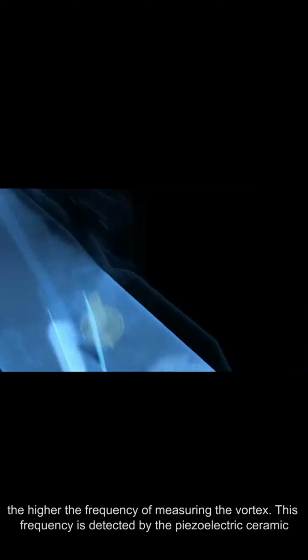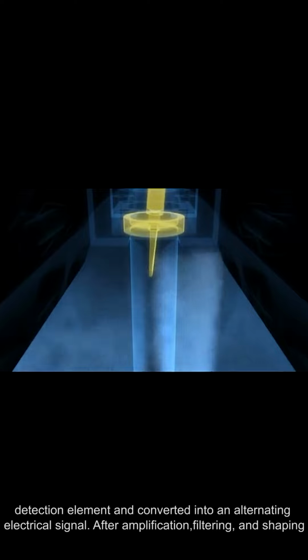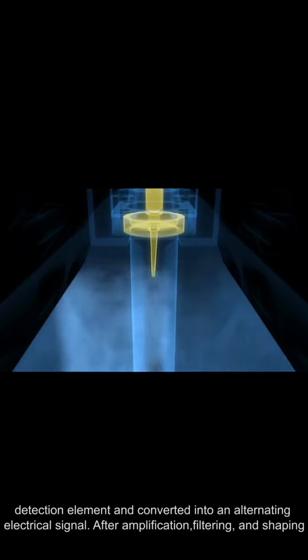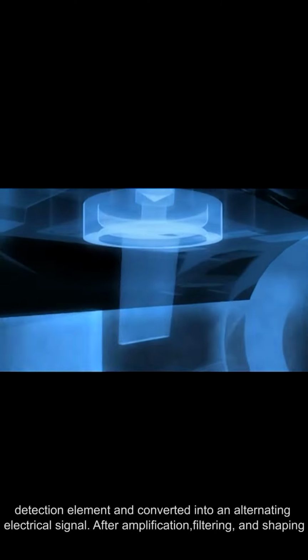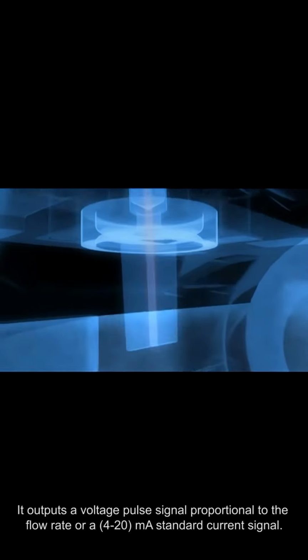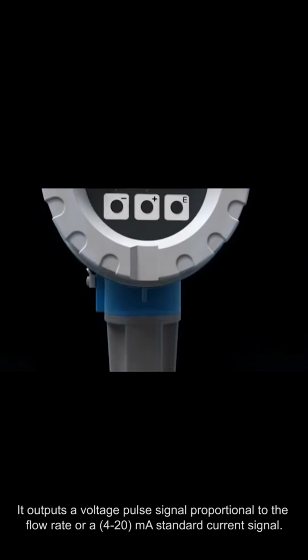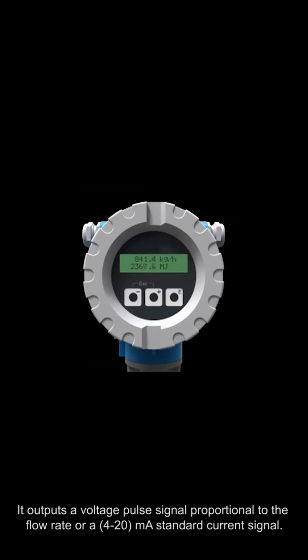This frequency is detected by the piezoelectric ceramic detection element and converted into an alternating electrical signal. After amplification, filtering, and shaping, it outputs a voltage pulse signal proportional to the flow rate or a 4 to 20 mA standard current signal.